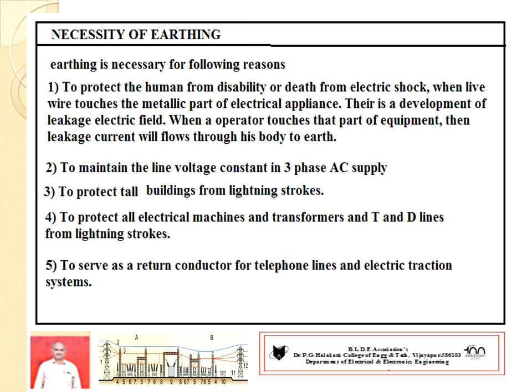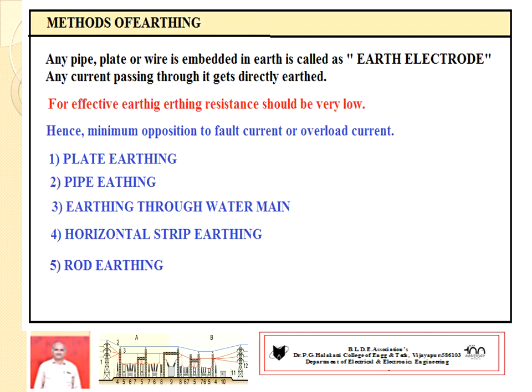Hence, to protect all the electrical machines that I mentioned, the electrical machines used in generating stations, such as AC generators and transformers, and T&D lines are all to be earthed to protect them from lightning strokes. Then earthing also acts as a return conductor in telephone lines and electric traction systems, that is, electric trains. So, as already known, we make a connection of a conductor from the electrical appliance to the earth point. Whatever connection we give inside the earth, that conductor is known as the earth electrode. The depth at which we embed the conductor and give the connection, that conductor is known as the earth electrode. Earth electrode may be of different types.